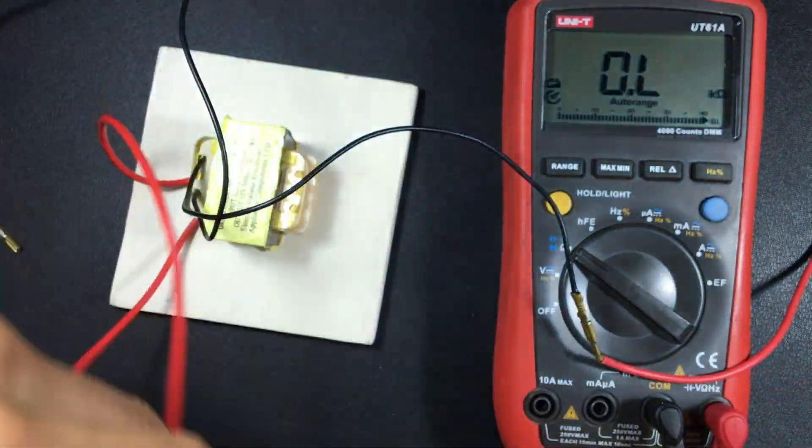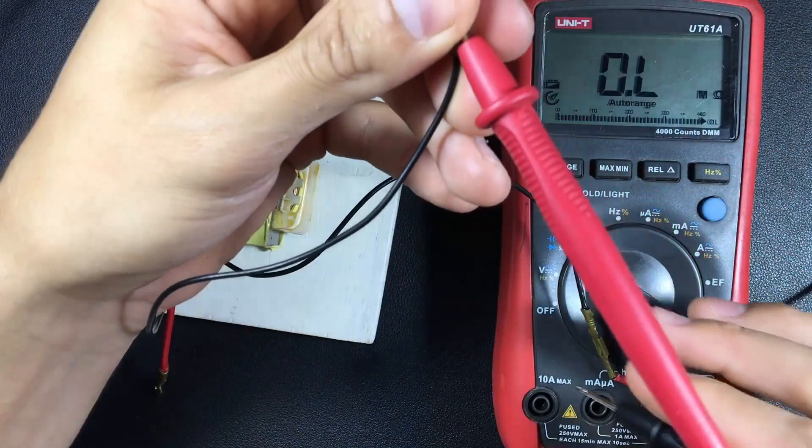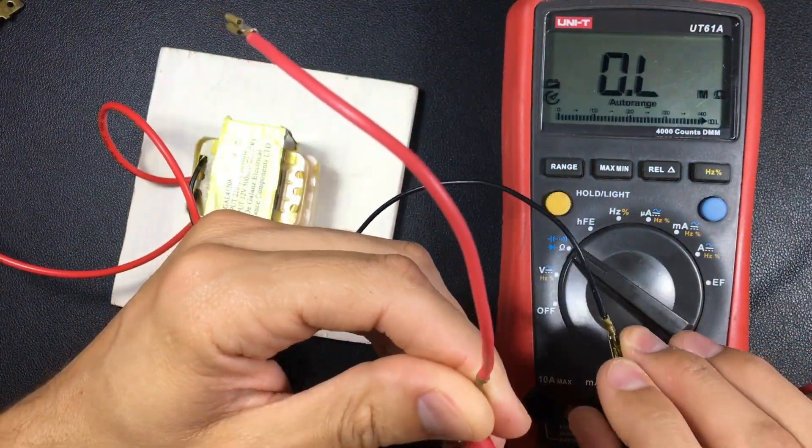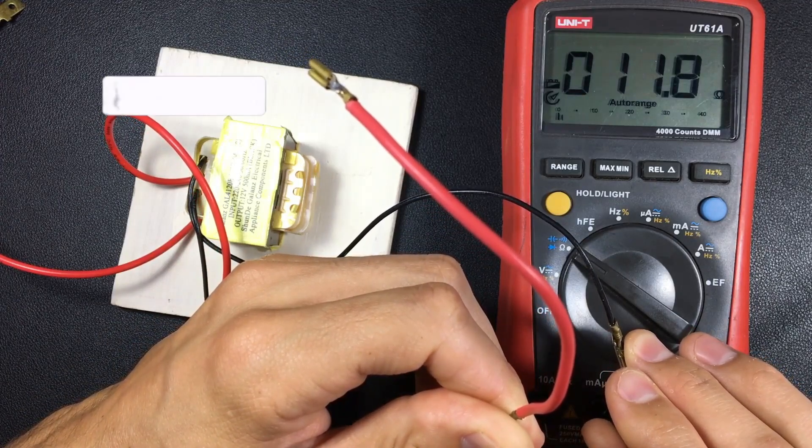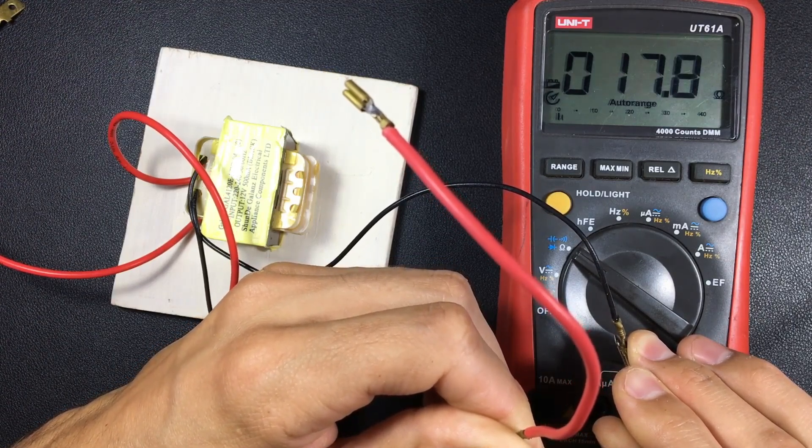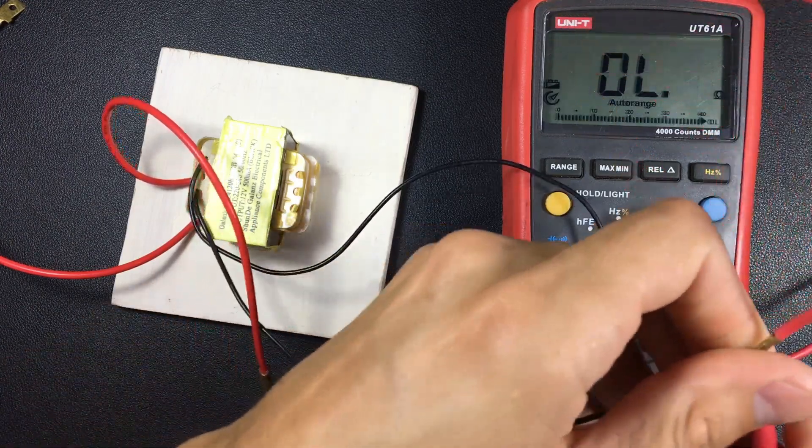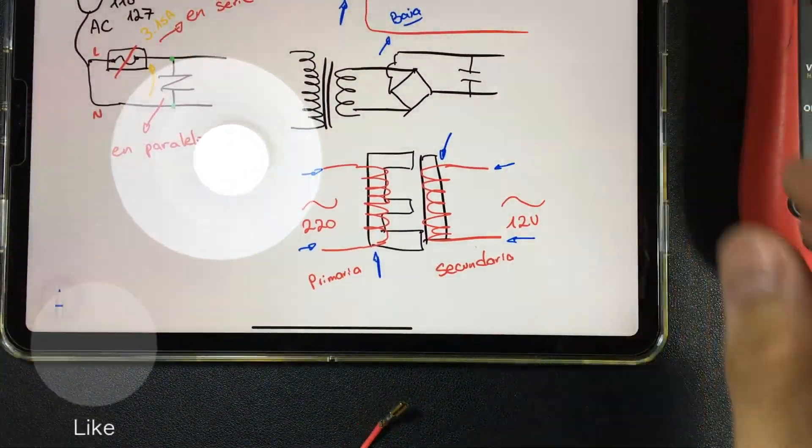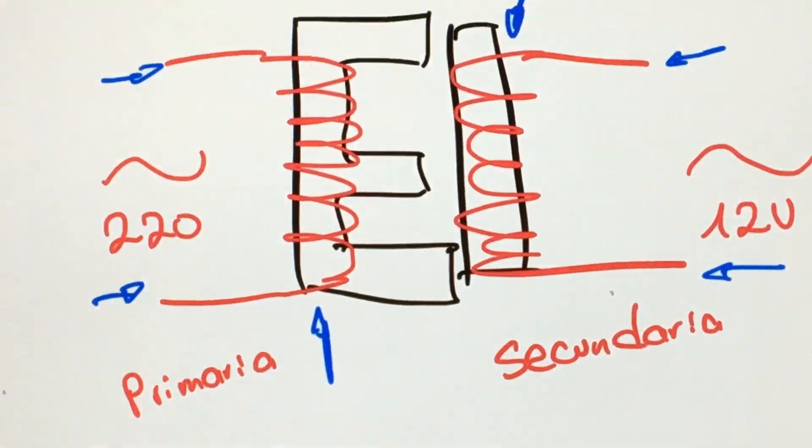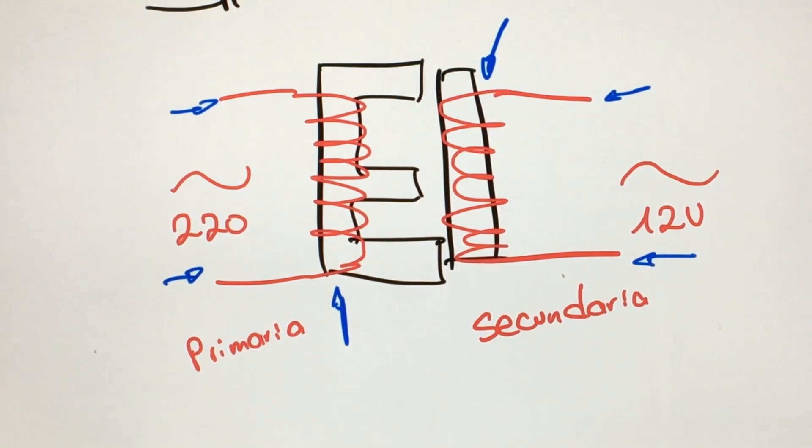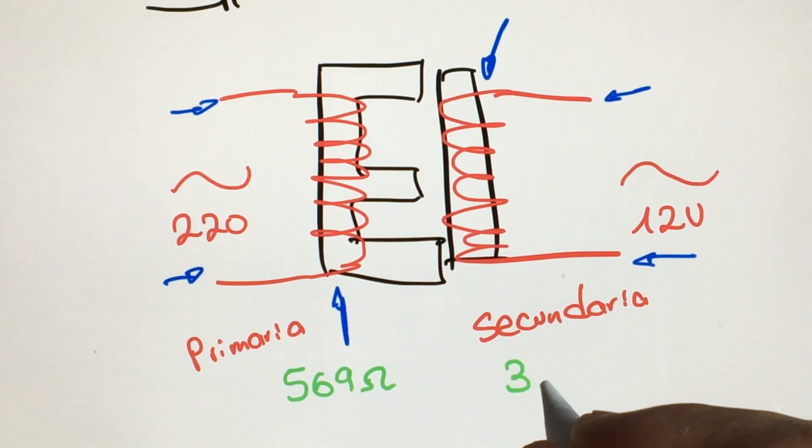We are going to confirm the secondary side. And on this secondary side we now have approximately 3 ohms. What does this tell us? Let's draw it to understand it better. On the primary side we find 569 ohms, and on the secondary side we just found 3 ohms.